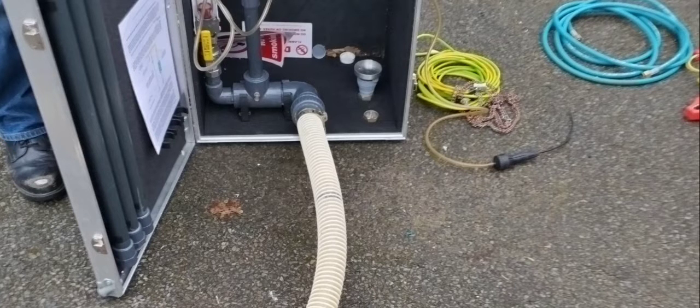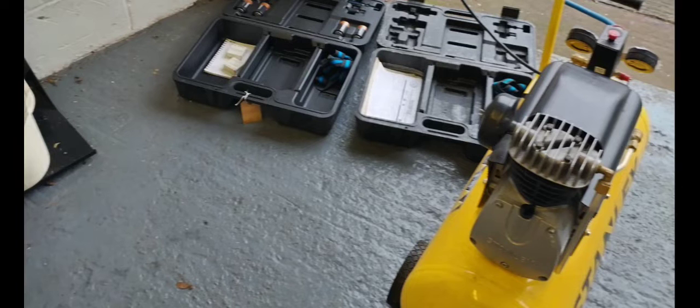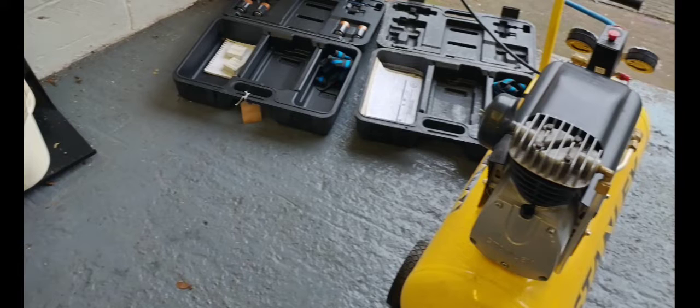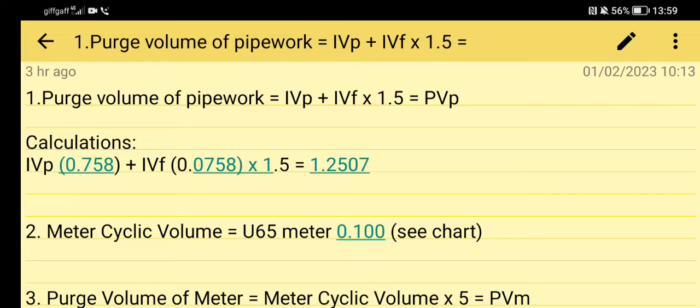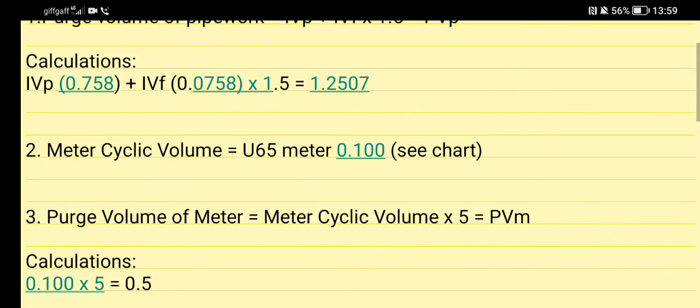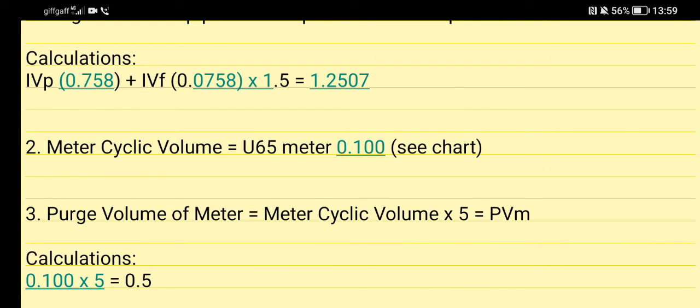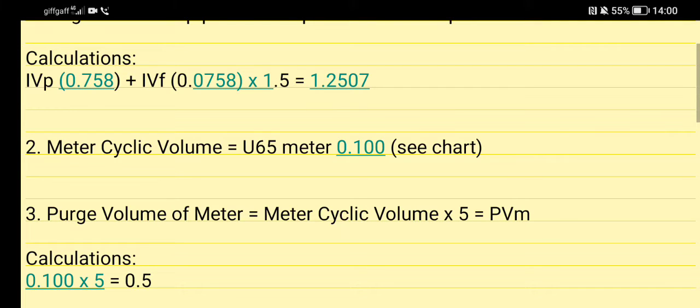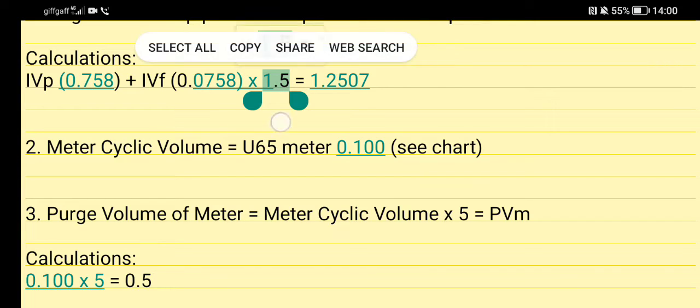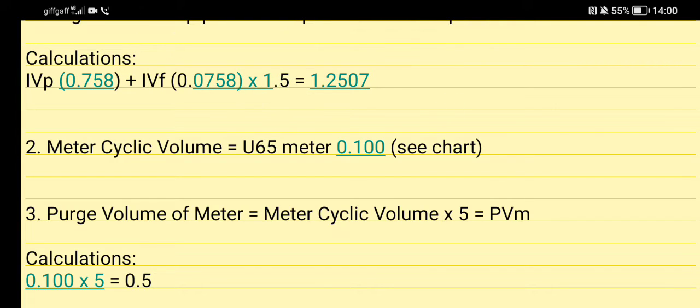This is our compressor here when we're purging from gas to air. Step 1: Purge volume of pipework - IVP plus IVF times 1.5 gives you your PVP. Here's the calculations: 0.758 plus IVF 0.0758 times 1.5. Remember to hit the equal button before you times 1.5. I will change that in the notes in the description and in the comments.